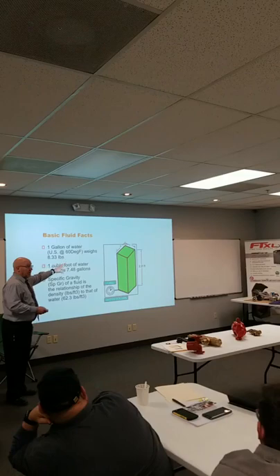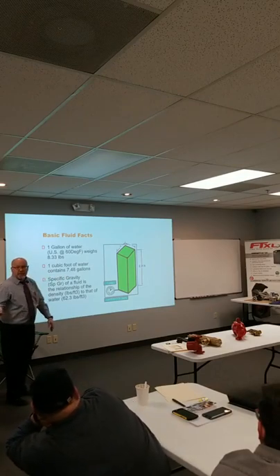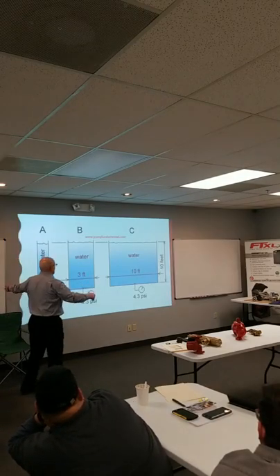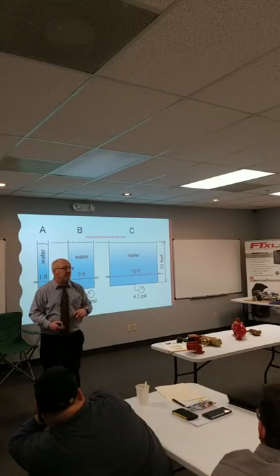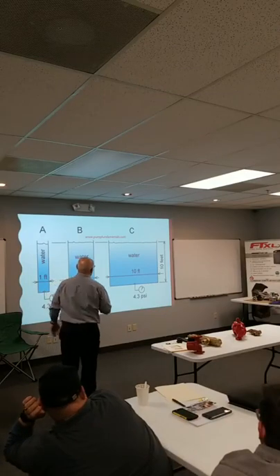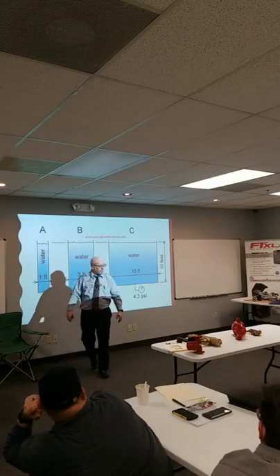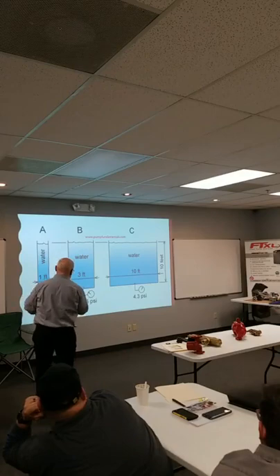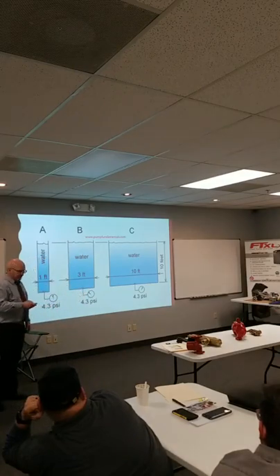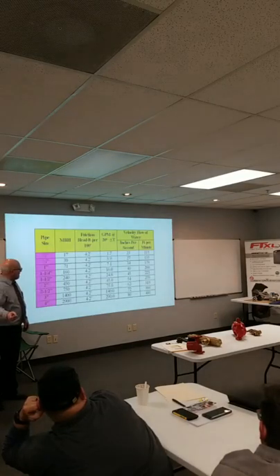Remember, water column? And this is whether it's a 1-inch pipe or a 10-inch pipe. I don't care how much water column it is or how wide it is, the height of the water determines that pressure at the bottom. Okay? So 4.3 PSI is 10 feet. 43 pounds per 100 foot. Okay? It doesn't matter what size the piping is. And specific gravity has something to do with it, but we're getting deep in there.